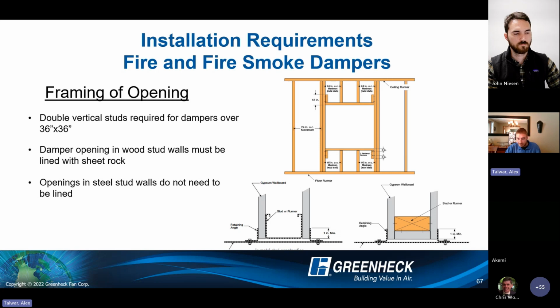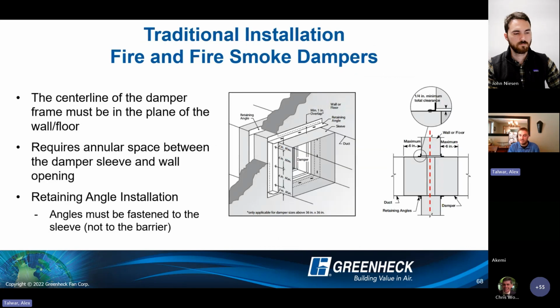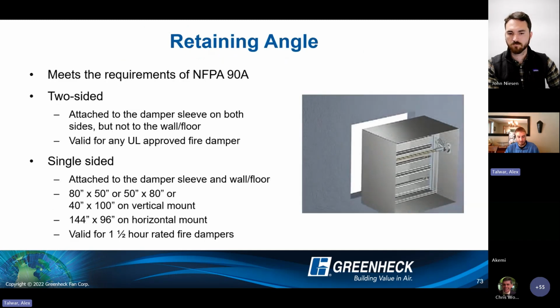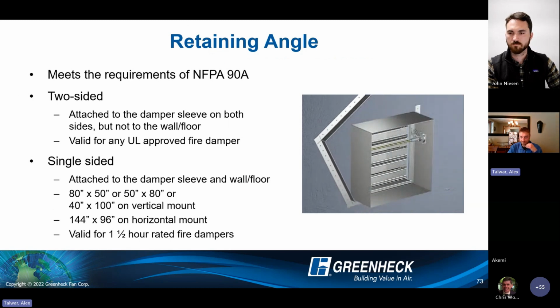This is installation stuff. The important thing here is that traditionally the damper needs to be within the plane of the wall, right? So the center line of the damper frame needs to fall somewhere within the thickness of the barrier. If you do need to be outside the plane of the wall, that's what those out-of-wall dampers are for. And we are using retaining angles to secure the damper in place. We do need to make sure we are following the manufacturer's installation instructions. All those instructions call for retaining angles. There are a few different methods that we can use, but I do not have time to talk about many of them. So I'll just leave it here.